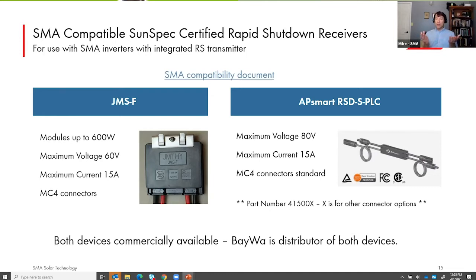SMA goes one step further. We know that the certification from SunSpec covers all of the requirements for compliance with 690.12. SMA wants to make sure that use of these devices in no way compromises the other safety functions and all of the operating characteristics of our inverters. So there is further a SMA compatibility document, which is linked on this slide, that says these devices not only are certified by SunSpec, they have gone through SMA's compatibility testing and are fully compatible with all of the inverter functionalities while providing full code compliance for rapid shutdown. Both the JMS-F and the AP Smart device are on that list.